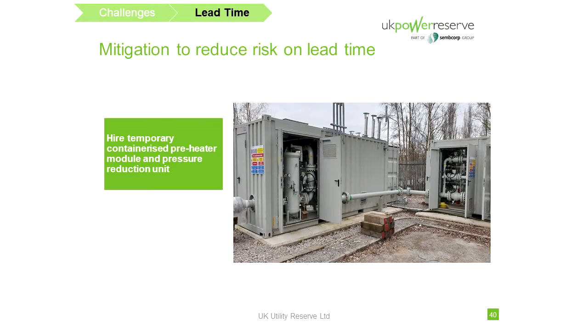To mitigate the risk of the lead time, so I've got 24 months, that hasn't gone away regardless. So the key strategic decision I had to take was, instead of installing that as a permanent solution, I hired a temporary containerized preheater from Netherlands, ensuring that it goes through all design approval stages, and that's what it looks like on site. So we've got the preheater module and the pressure reduction station.